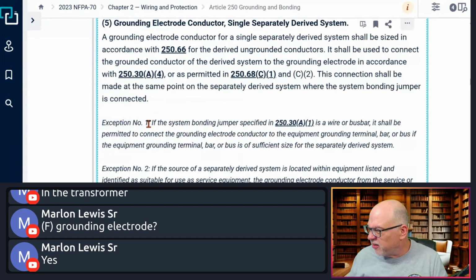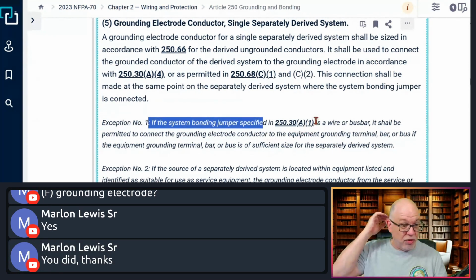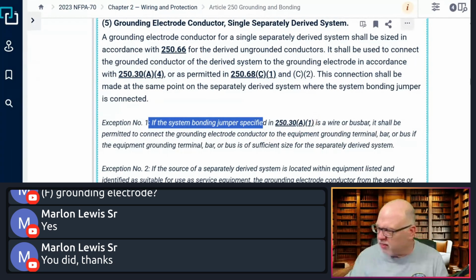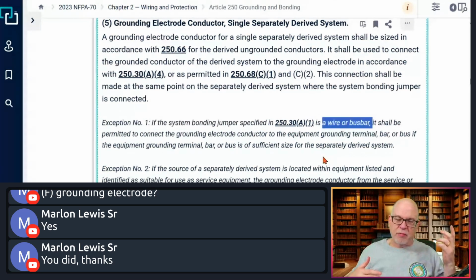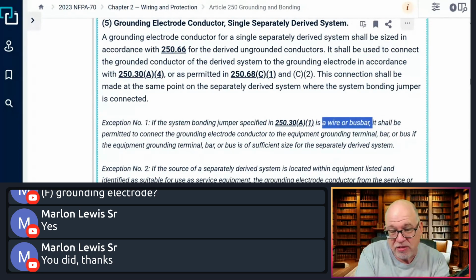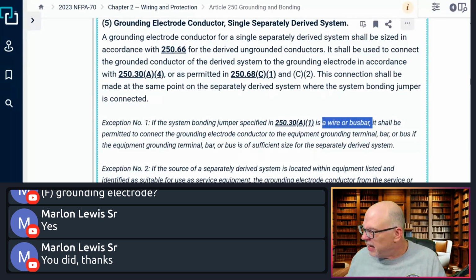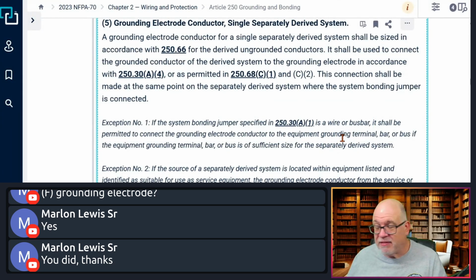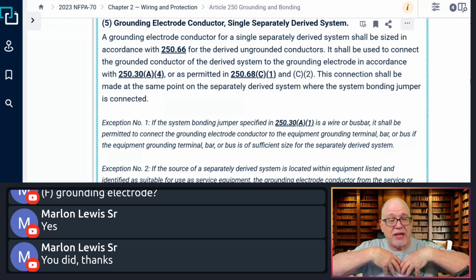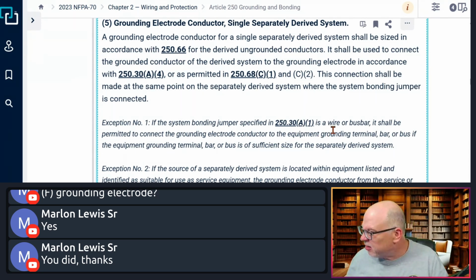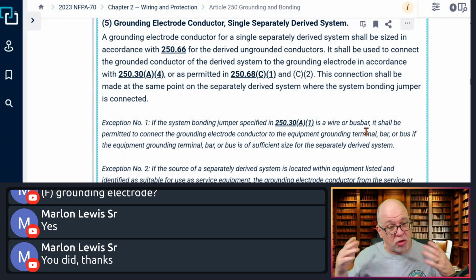It says, if the system bonding jumper specified in 250.30(A)(1), so that's the single separately derived system, is a wire or bus bar. A beautiful thing with a wire or bus bar, because that typically means that you size something. Maybe it's even a bus bar that's provided by the manufacturer, where no sizing would be required because they're providing it. But if it's a wire, we have to size it, so we've got to know what we're doing. And that's why I like to show the separation in wires, because it forces you to size things.